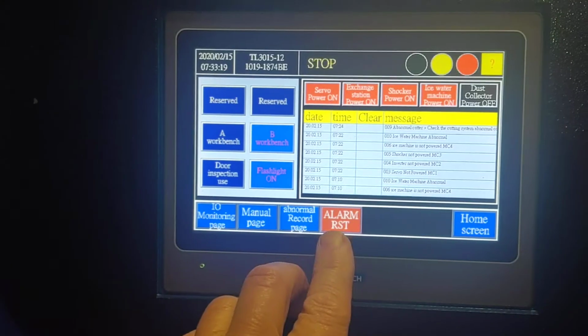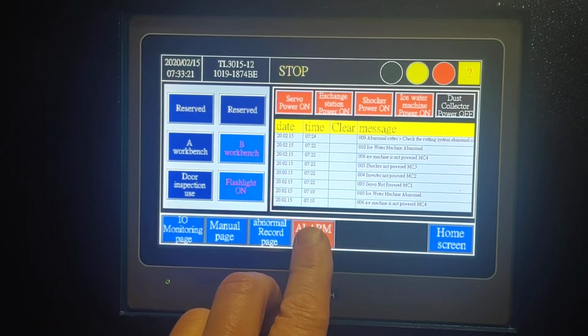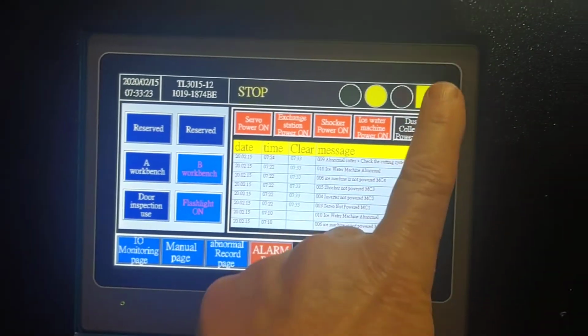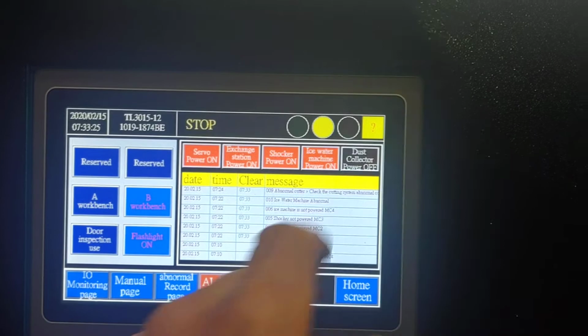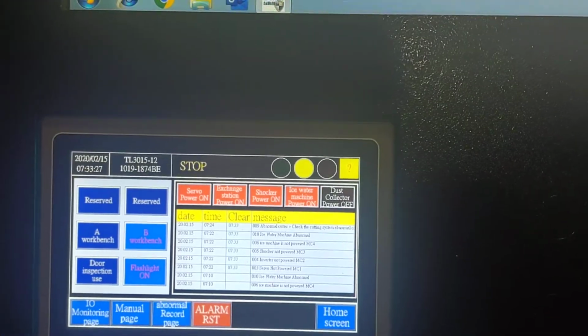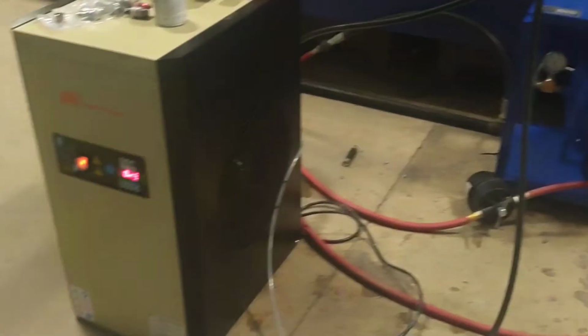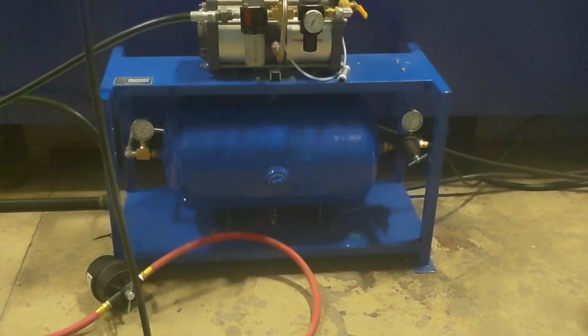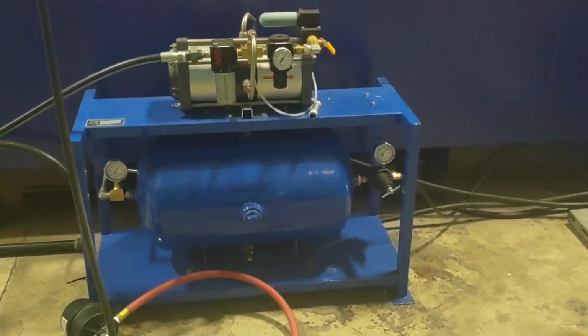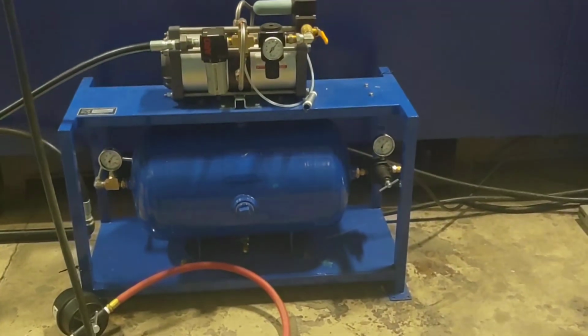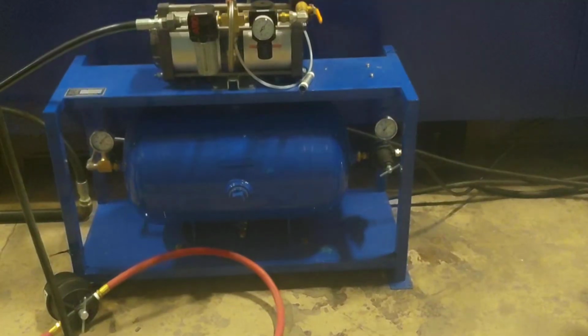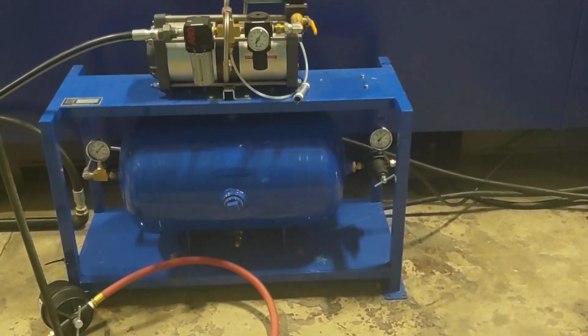I've closed the doors. I need to reset this alarm, which will occur when I open the doors, so I need to reset this. This light needs to be dark. My air dryer needs to be on, and whichever method you're delivering your gas, you need to have your air on and ready. In this case, I have an air amplifier, and I'm over 200 psi on my output. So my air is ready.